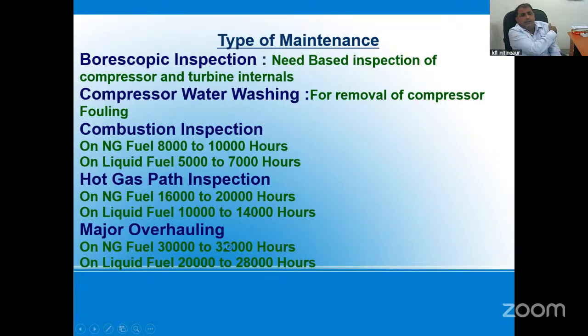Major overhaul. After completion of 30,000 or 32,000 hours, major overhauling is scheduled. Major overhauling means combustion inspection, hot gas path inspection, and every other part, means flange to flange, from one flange to another flange of the gas turbine, all the parts should be inspected. During the major inspection, the machine is dismantled totally. Every part is taken out, inspected, replaced, whatever required.